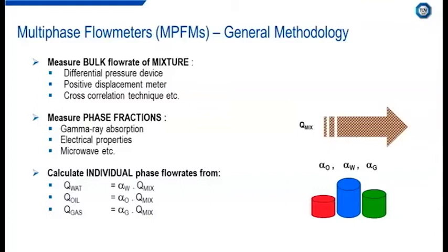Secondary sensors must also be used in order to measure the individual phase fractions of the multiphase mixture in addition to the measure of the bulk flow rate. In order to determine the individual phase fractions, a number of methods could be used, such as the gamma ray absorption technique, which gives an indirect measure of the density of the phases, or the use of sensors which measure the electrical properties of the fluid, and microwave techniques, taking advantage of the differences in permittivity and conductivity of the oil and water phases. Knowing the phase fractions of oil, water and gas, as well as the bulk total mixture flow rate, individual flow rates can then be calculated.